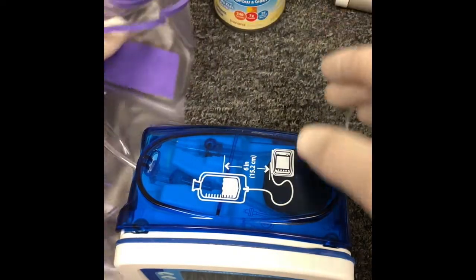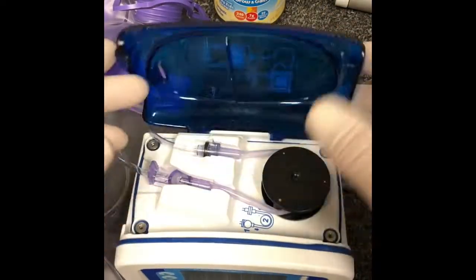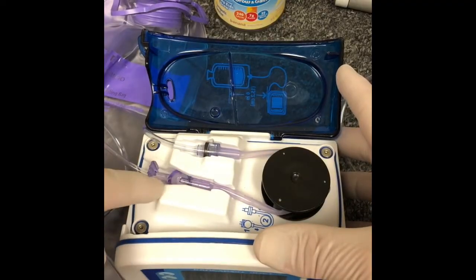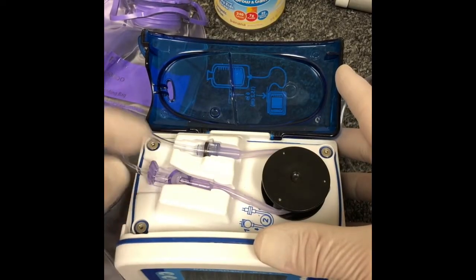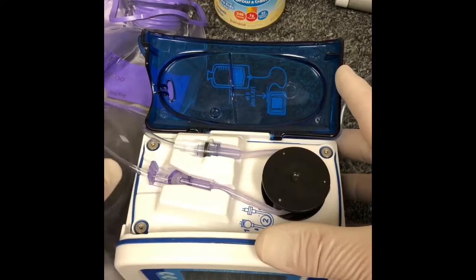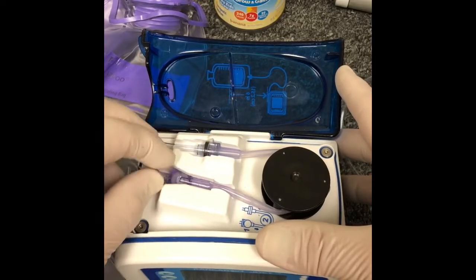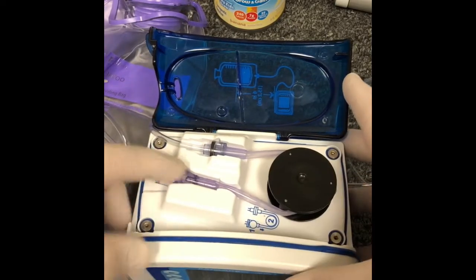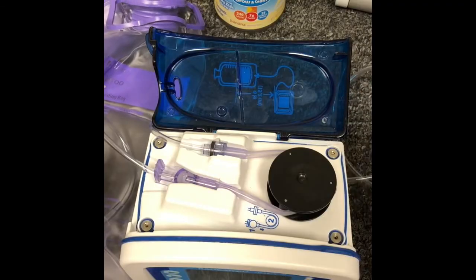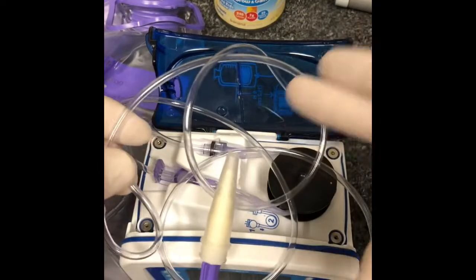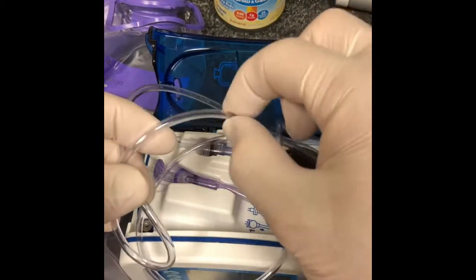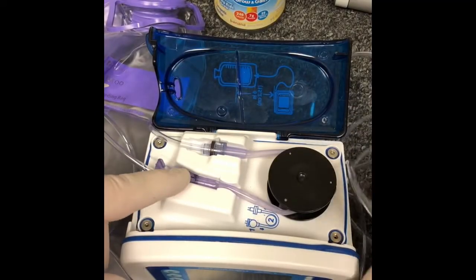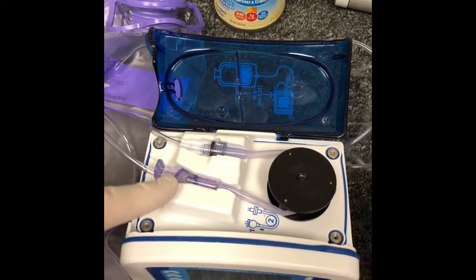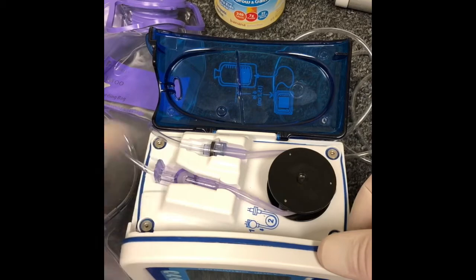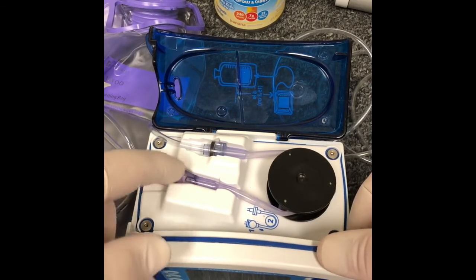Right now there's a flow stop. This device is basically stopping any flow. So even if you were to pour the formula in with this not secured in the pump, it will still stop the flow, so you don't have to worry about any free flow. If you notice, there's no clamps on the line, no clamping device at all, because this section has a flow stop happening. So right now there's no flow happening through the tubing. It is stopped up by this device.